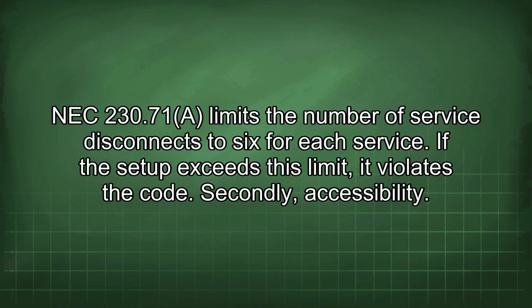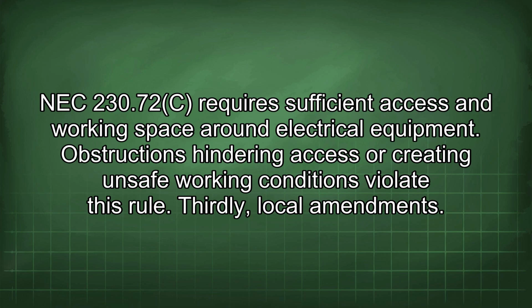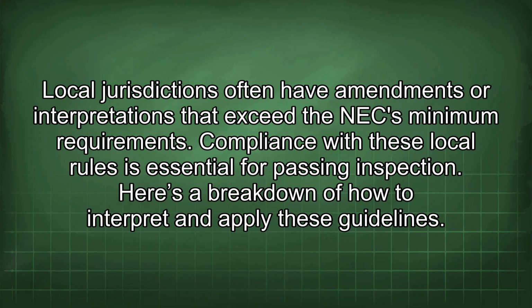Secondly, accessibility. NEC 230.72c requires sufficient access and working space around electrical equipment. Obstructions hindering access or creating unsafe working conditions violate this rule. Thirdly, local amendments. Local jurisdictions often have amendments or interpretations that exceed the NEC minimum requirements. Compliance with these local rules is essential for passing inspection.